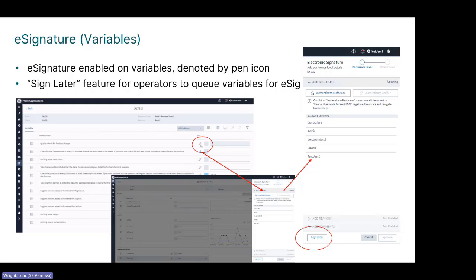Another thing we hear a lot about is the need for electronic signatures. You have the capability of adding this as part of an additional variable, and you can configure one or two levels — it could be your operator, or an operator and a supervisor. They use their system logins, are added as available verifiers, and can see that this requires an electronic signature by the pen symbol. You click on that, a pop-up opens, and you click authenticate performer — one or two may be available depending on configuration.